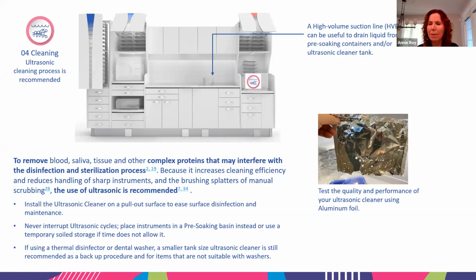Doug, do you recommend testing the performance of the ultrasonic cleaner on a regular basis? Yeah, I would recommend doing that test once a month because unfortunately what happens with everybody's ultrasonic cleaner, if you have a transducer, some smaller units have one transducer, a lot of the medium to larger size will have two or more. And should you experience any issues where a transducer goes down, it doesn't sound any different, it doesn't feel any different, but one of the transducers is not operating.